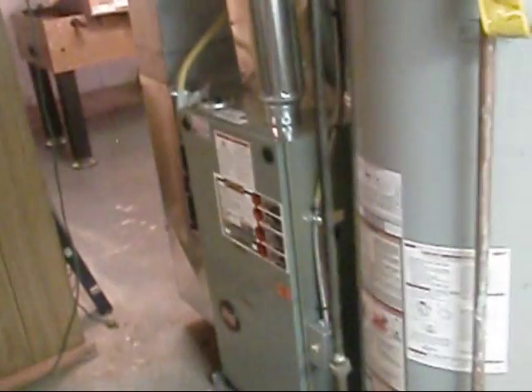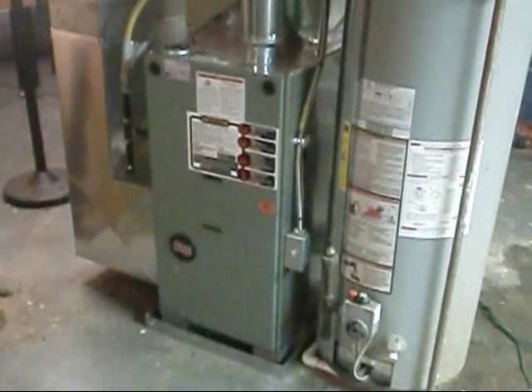We're wrapping it up over here at Charlie's. Didn't get the static where I wanted it to be, but I definitely got the temperature rise exactly where I wanted, and if it wasn't for cutting those returns in, I wouldn't have got it — I was burning way high last time. Like I said, those returns are just temporary until Charlie can get the money together to run some additional ductwork so we can get returns out of the bedrooms upstairs. I'll holler at y'all later, thanks for watching.